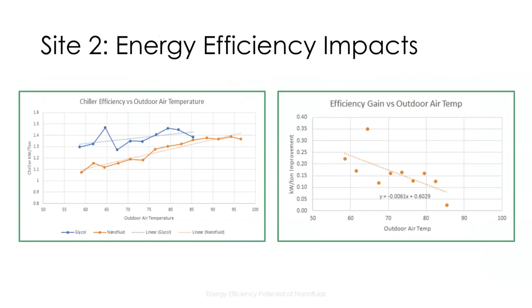These are some graphs similar in design to the previous site. The left-hand graph shows a general trend that could be more or less what was expected, with the blue line efficiency being higher than the orange line. So in both cases, it shows that the system's less efficient at higher loads when it's warmer outside.